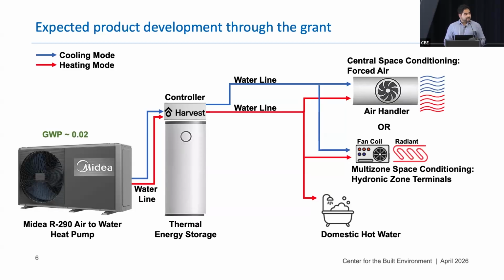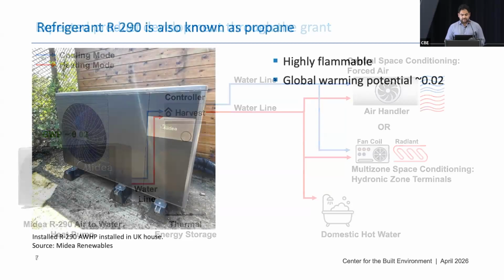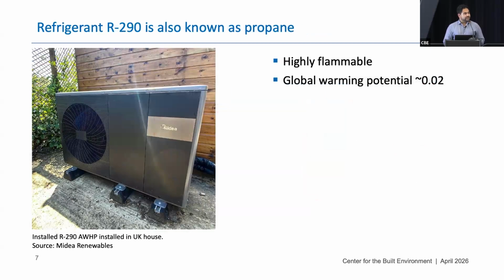The GWP in this particular unit is less than 1, so it seems like a good system or good design, but the main concern with R290 is that it's also known as propane, a highly flammable refrigerant. But it's highly desirable for HVAC equipment because it has a very low global warming potential, like I already discussed.